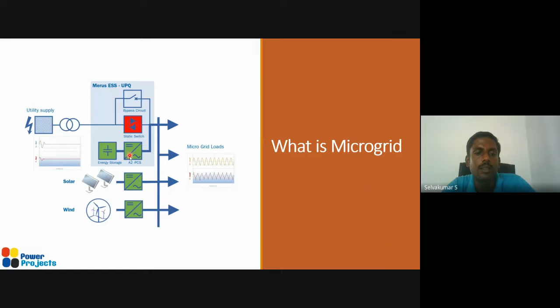So now, if you have this energy storage, during the grid failure there is a seamless transition, which means the loads which are connected will never see any interruption. As soon as the grid fails, this will come and take charge, setting the reference voltage, maintaining the frequency, taking care of all the mismatch, and maintaining voltage and frequency. And the user here will not really understand whether the power supply he is getting is from the grid or only from the local grid. The grid has failed, but you will not see any interruption. It's like when you have a UPS in your home, you will not be able to realize whether the grid failed or not. In a similar fashion, this battery energy storage with the bidirectional converter can help you on that.